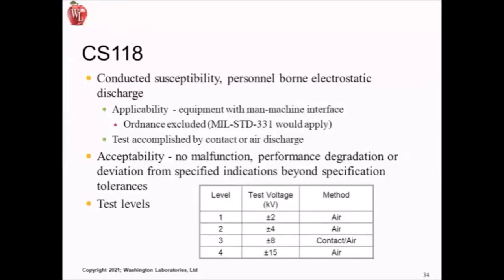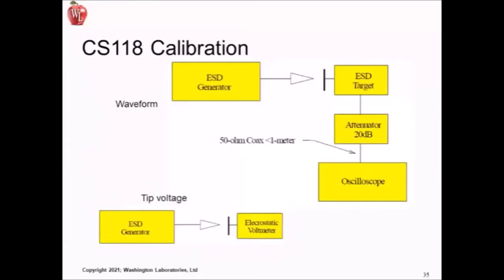CS118 is new to MIL, at least over the last 5 years. As I mentioned before, it's been a commercial spec for as long as I've been doing this kind of work. 801-2 was the first IEC spec that had personnel waveforms. So there is a particular type of discharge, and there is a particular type of calibration that's required in order to make sure that you have the right voltage level at static level. You use an electrostatic voltmeter to check the tip voltage, and then you have an ESD target to make sure that the waveform has the right characteristics.